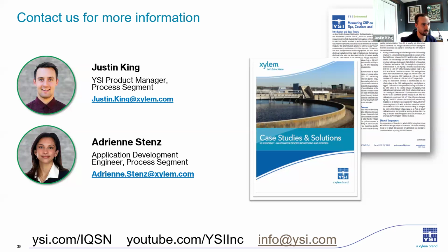Yeah, so as far as maintenance and training goes for our IQ SensorNet system, typically when we're setting up a new system, we offer some sort of training services, and we actually have a lot of online materials that cover the different calibrations that are needed to keep these sensors giving you reliable and accurate data. In general, we try to make our instrumentation as maintenance free or as maintenance light as possible. So for example, our FDO dissolved oxygen sensor is factory calibrated and does not need to be regularly calibrated throughout the lifetime of the sensor.